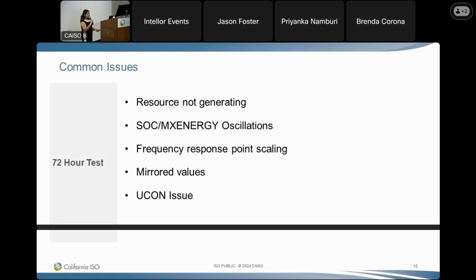Another issue we see commonly is state of charge and max energy oscillations. Please verify prior to requesting the 72-hour or COD test whether any of the data has oscillation or spiking issues. Also, for frequency response points we are seeing scaling issues, so please check that prior to the 72-hour test, whether there are scaling issues for the frequency response points or any other telemetry points in general. Ensure that the mirrored values are programmed correctly and don't have any issues, and that the logic for the UCON or AGC, all those logical points, are programmed and working well prior to the 72-hour test request.